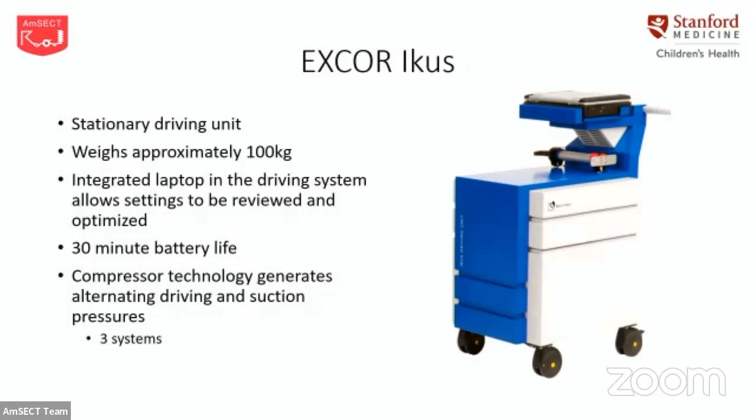And there are 3 systems in the Ikus. So what that means really, if you have a BiVAD, one compressor system runs the LVAD, one compressor system runs the RVAD, and then you have a third system that acts as your backup.